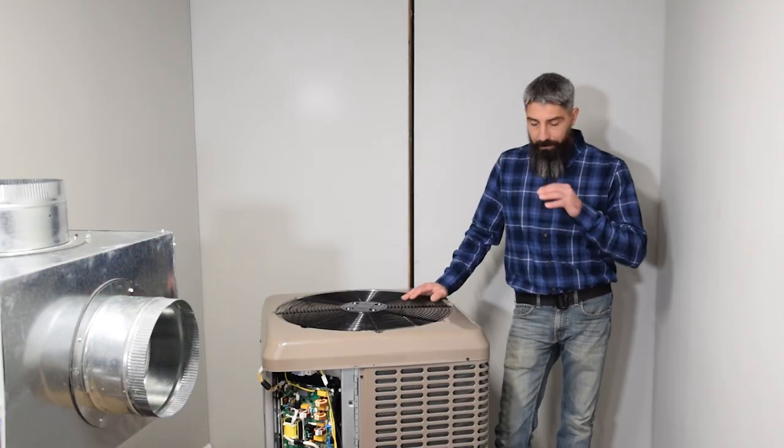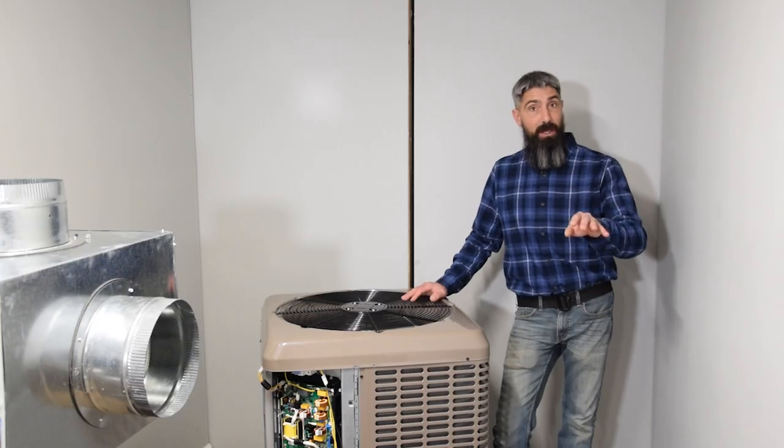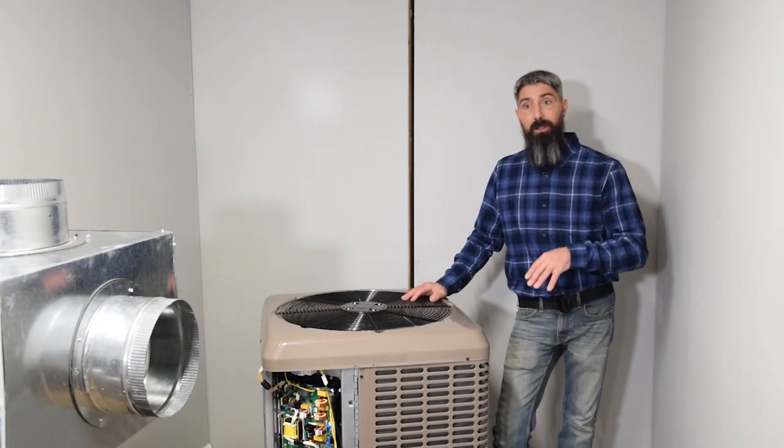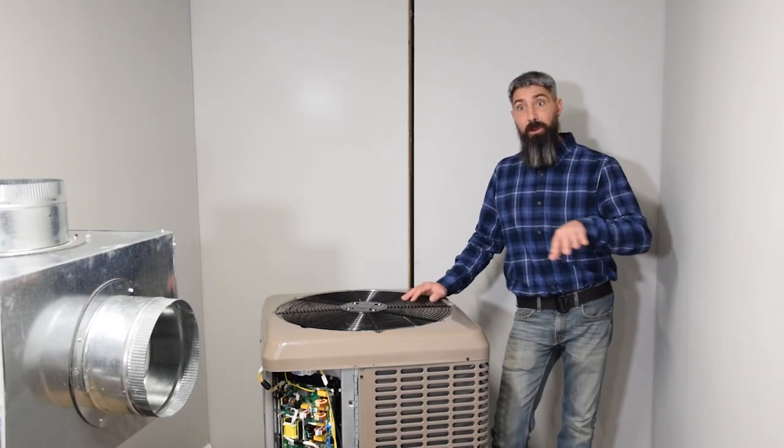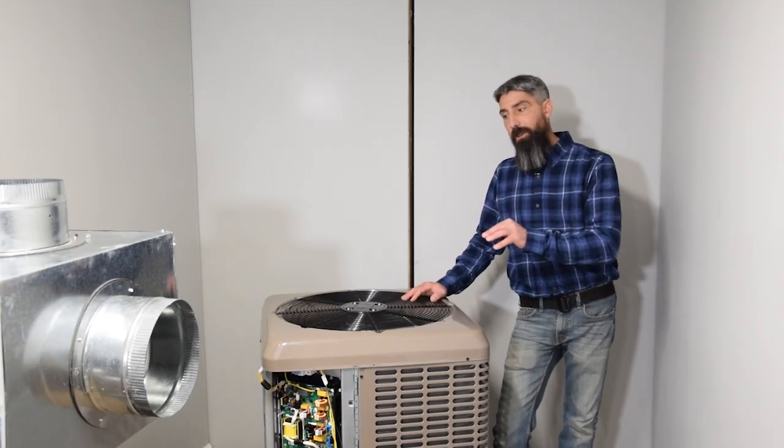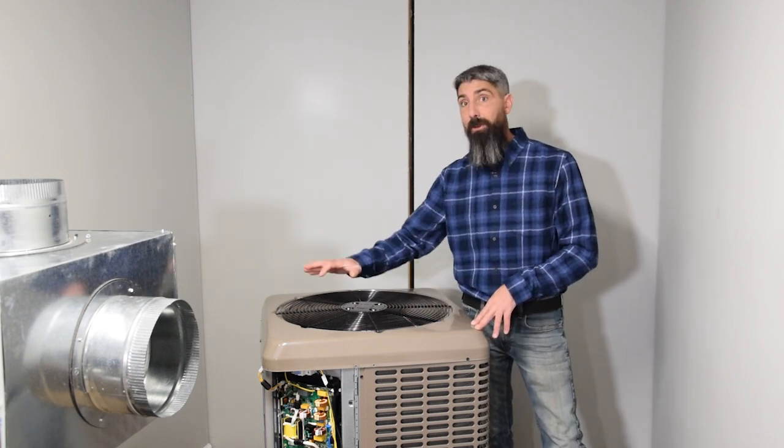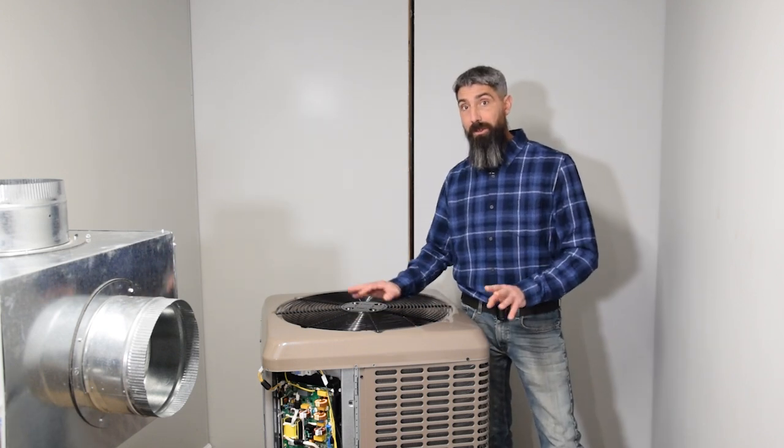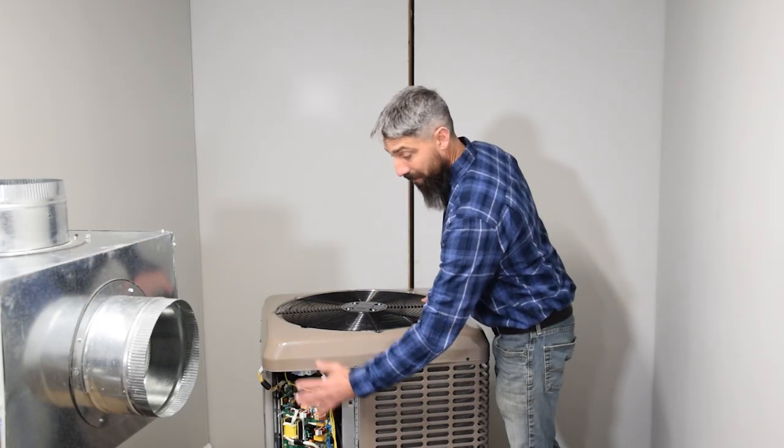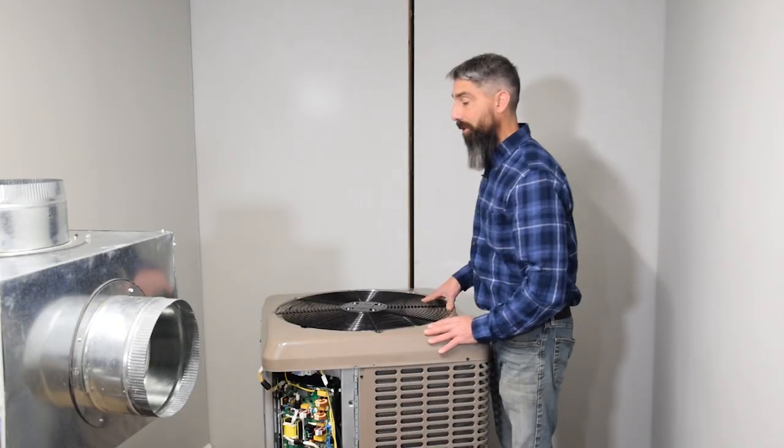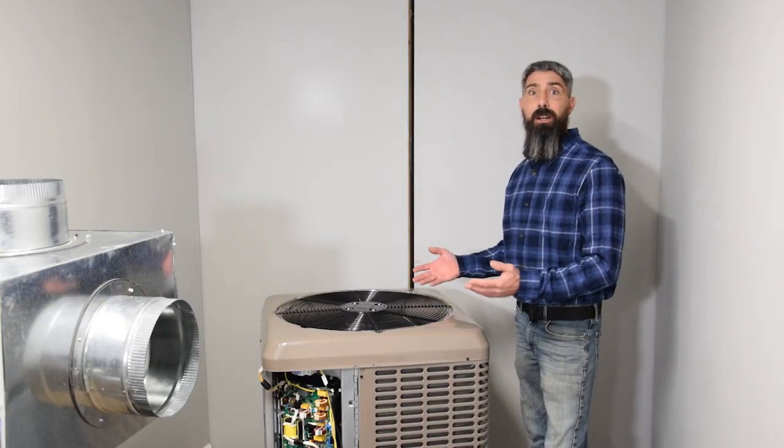All right. So here's where I've gotten some flack in the past from folks of just basic tips of how to take care of it and they say we're trying to scam you. I'm not. This is something legitimately that we will do going out to your house. First thing I'll do is pull the disconnect out. I'll make sure all power is off to the system. Must happen. Make sure the control panels are covered up because I don't want anything accessing the control panel. And I'm going to spray water on it. Not hot water.